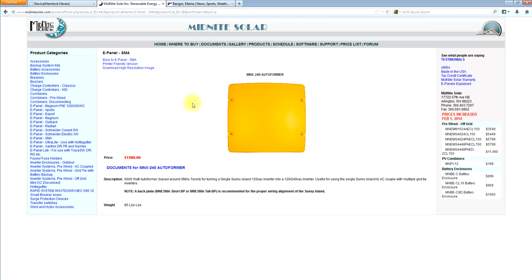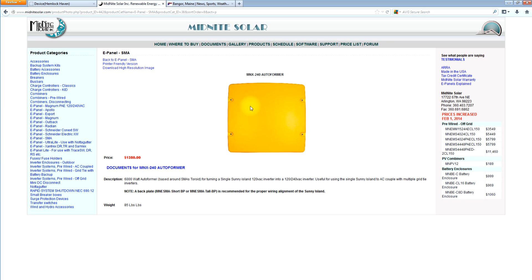Here is the autoformer. It fits on the back plate directly above the Sunny Island inverter. It does use the same toroid as the SMA Smartformer. We actually buy the toroids from SMA. And it's just in a little smaller package, a little less expensive, and fits together really neatly. So it's just like any other autoformer, only a little bit larger, and makes 240 volts from the 120 volt. Or it can step down a 240 volt generator to 120 volts.